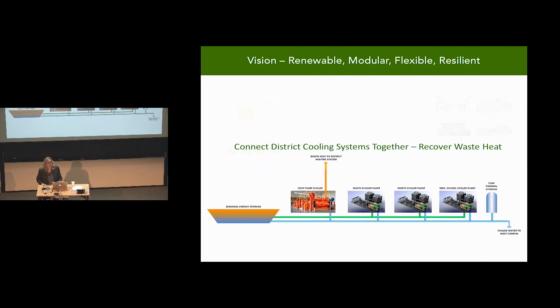As we need to add more capacity to those systems as cooling loads grow on the campus, we would add thermal energy storage, diurnal thermal energy storage, chill water storage, as well as potentially seasonal storage to that system in the future. And as we need to replace our existing cooling assets, we would propose to install heat pump chillers that could transfer heat from our heating loop to our cooling loop, or take the heat from our chillers and put it into our heating loop, depending on how you want to describe it.